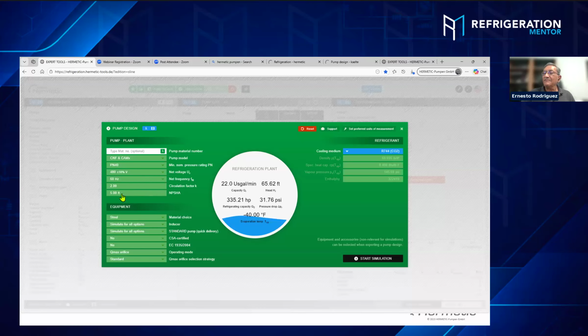I can go with 3 feet. Sometimes in some applications you need to size the pump for a very low level, 3 feet. It means the pump is going to handle very low levels without cavitation. I size the pump to handle very low levels. In this example, I want to go to 5 feet, approximately 1.5 meters.